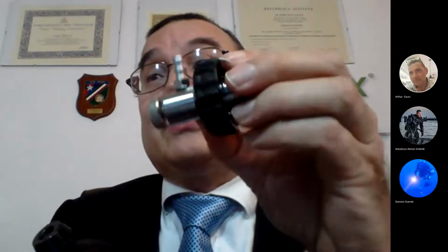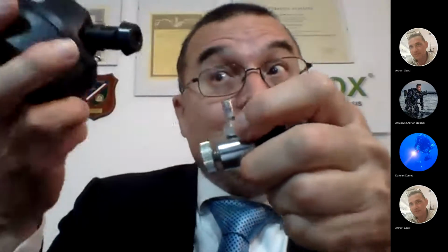But be aware that there are also other accessories. One of the best for sure is the flow restrictor. You connect this flow restrictor to the cylinder, then you have inside the stainless needle valve, then you gently turn on, and then you have a flow at constant temperature, constant pressure, and constant flow. That is the best way for making the analysis. Now we are going to do the analysis a different way, and then you will see the difference in the analysis.